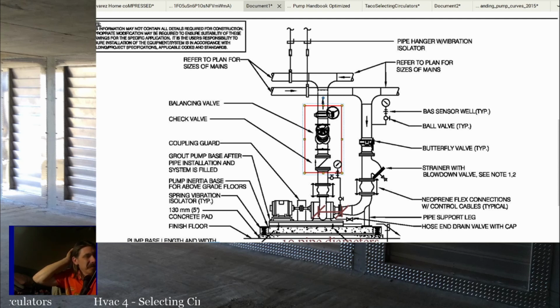So, yeah, you definitely want to. I mean, generally, I don't start up a pump until I've got the system bled of as much air as possible and at design pressure. You know what I mean? And when you're dealing with dry coolers, I know a lot of times those pumps are on the roof or something like that. So they're basically working under a very small amount of pressure anyway, because you're at the top of the system where the pump is at. But you want to have that whole tank filled up and everything and try and get as much of the air out as you can as you're filling, and then start it up.